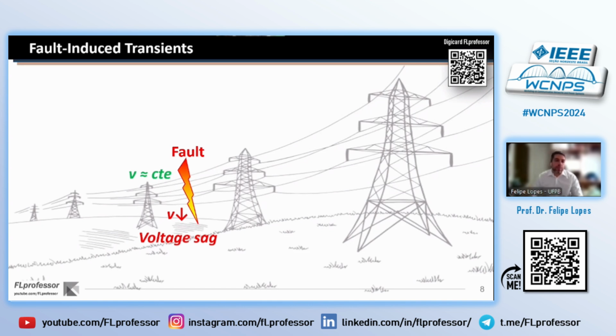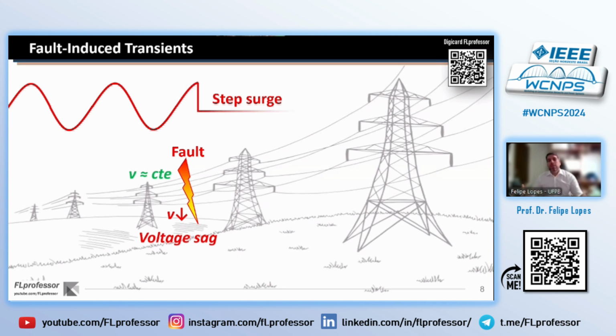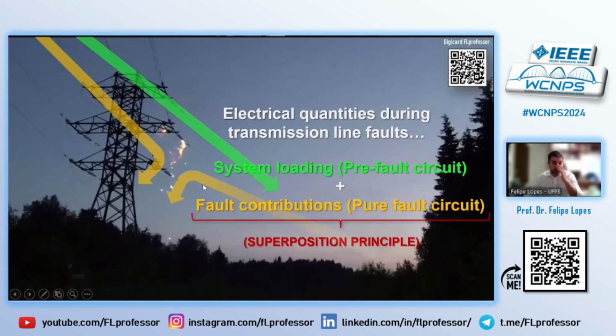And at the fault point, it is expected to occur an abrupt voltage variation, an abrupt voltage sag, in such a way that we can see a step surge. But thinking about this step surge, thinking about this waveform here, which will appear at the fault point, we have to remember that fault quantities, electrical quantities during transmission line faults, are the superposition of system loading and fault contributions.